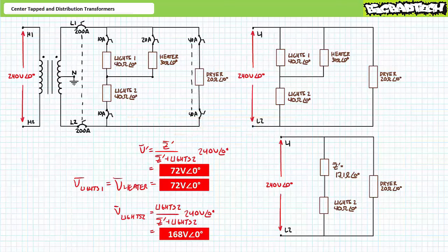The loss of the neutral connection has fundamentally changed the behavior and configuration of this system. It is for this reason one might observe odd behavior in a system lacking a neutral connection — such as unsteady lights flickering and dimming, or crazy motors surging and dying as loads are connected and disconnected. Not only does the neutral line carry imbalance current in the event of load imbalance between phases, it also serves to ensure single phase loads have access to a fixed potential.